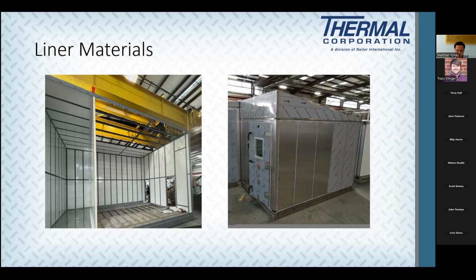But there's a lot of different options to consider. You can do tread plate on your floors, 1/8 inch or 3/16 inch tread plate for access with large units that you're walking in. You don't want the servicemen going in there and slipping on it and falling. It's more of a safety thing. With the tread plate floors, you can also do what we call wash down floors, where you'll take that tread plate and upturn the lip on the collar and have a 2-inch collar going around the perimeter of the floor.